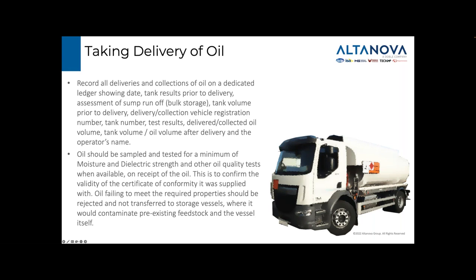As a minimum, test delivery oil for moisture and breakdown voltage before signing for the delivery. If the oil doesn't meet specification or closely match the certificate of conformity data, then reject the delivery, else it may contaminate your existing feedstock of oil. Once this mistake is made, it's difficult to establish if your oil storage facilities or oil supplier is at fault.